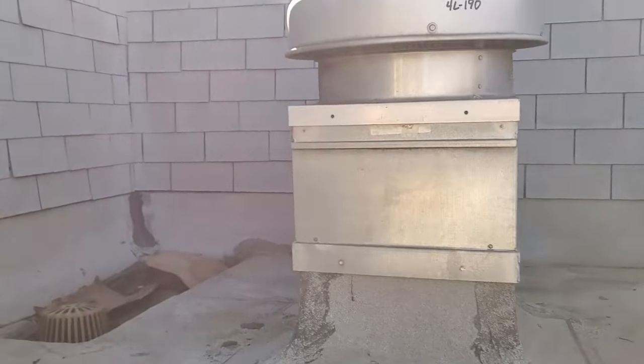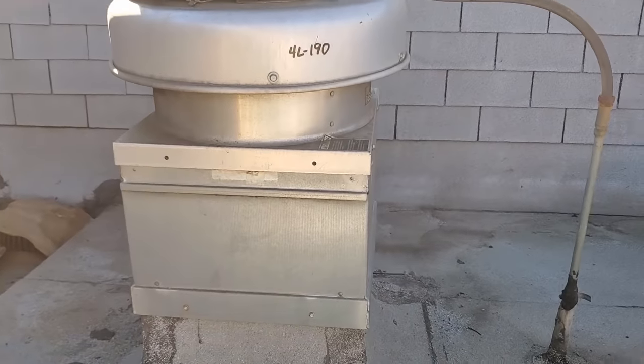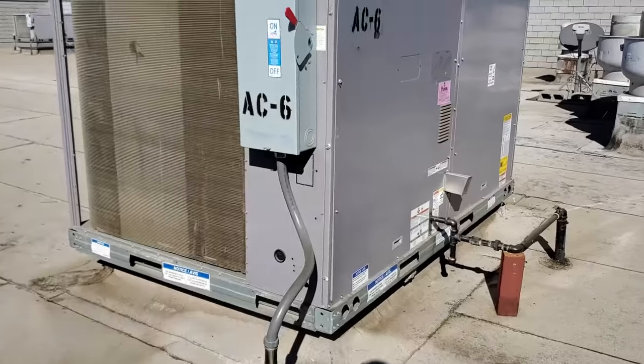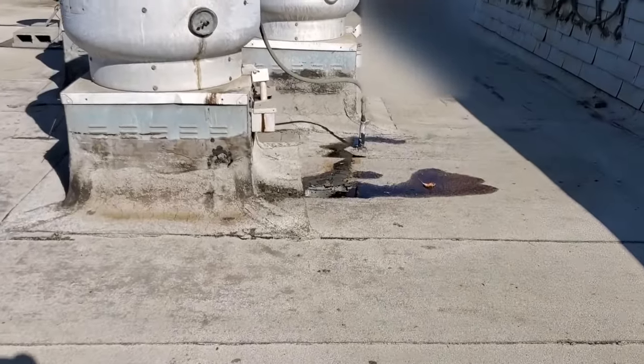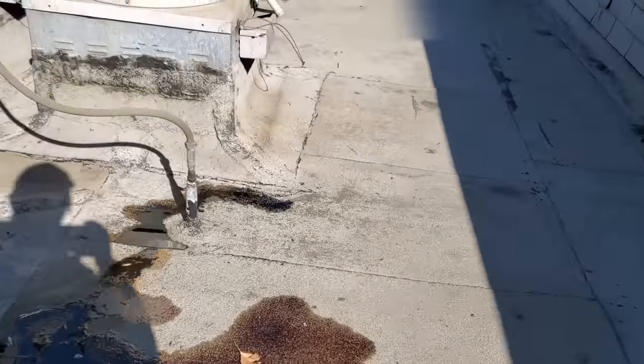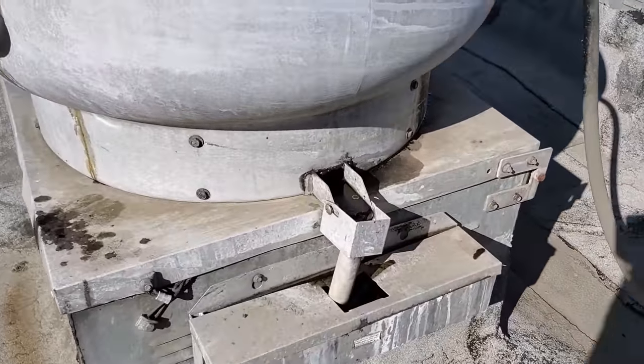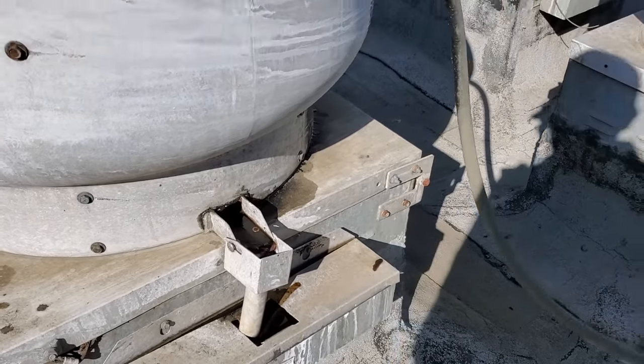Today I'm told that their dishwasher exhaust fan is not working properly. So we're going to come over and try to find their dishwasher exhaust fan. Looks like there's some nice grease buildup. Grease trap is overflowing — we'll have to let their facilities department know about that. That's dangerous.